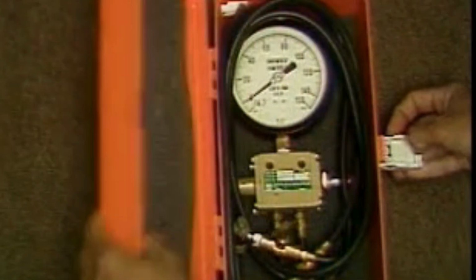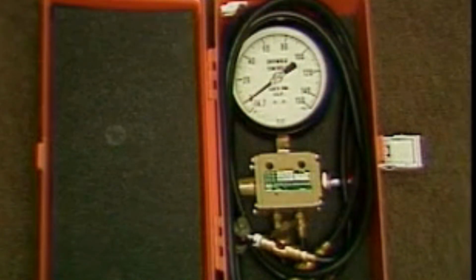Each automatic flow control valve kit consists of a 1/4 inch by 2 inch minimum size nipple. Also, the manufacturer provides a metal identification tag with chain for each valve. The tag is metal, stamped with zone indications, valve model numbers, rate of flow, GPM, and differential pressure ranges. Flow measuring instruments are also furnished by the manufacturer. These are to verify and check the flow rates. The correct flow is verified by establishing that the operating pressure differential across the valve tappings is within the range indicated on the identification tag.